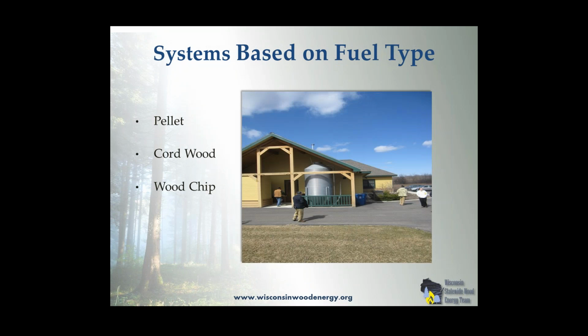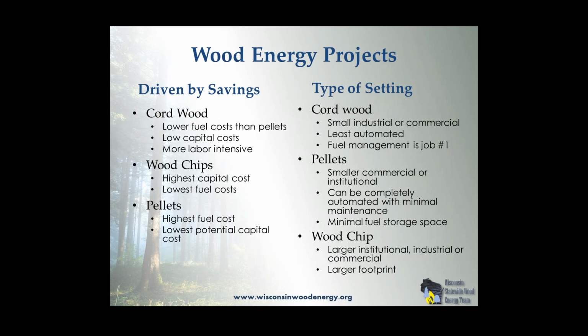So the system and the cost of the system really is based on fuel type. And typically the way we like to divide these up, if you look at cordwood systems, they're small systems, usually minimal investment. They're more labor intensive, but the opportunity is there. And usually the fuel is either produced on site, or they've got some relationship with the fuel provider in most cases where we put in these systems. It's a little bit cheaper than pellets, but it's always more expensive than wood chips, simply because of the capital or the intensive labor that it requires to harvest and handle and move it. We try to design systems that minimize the number of times you have to handle the cordwood.